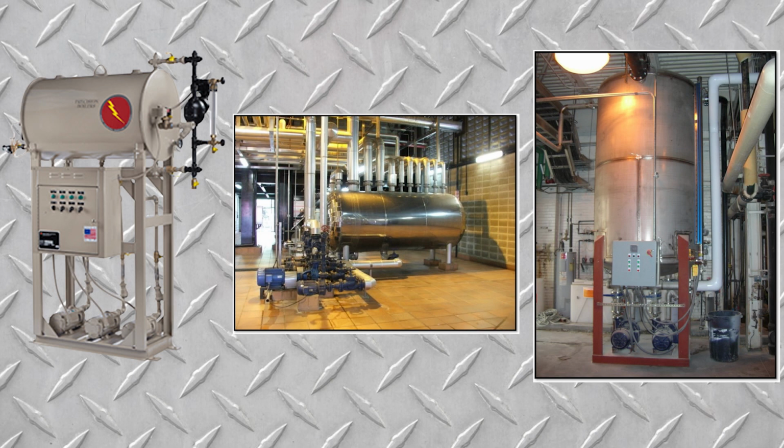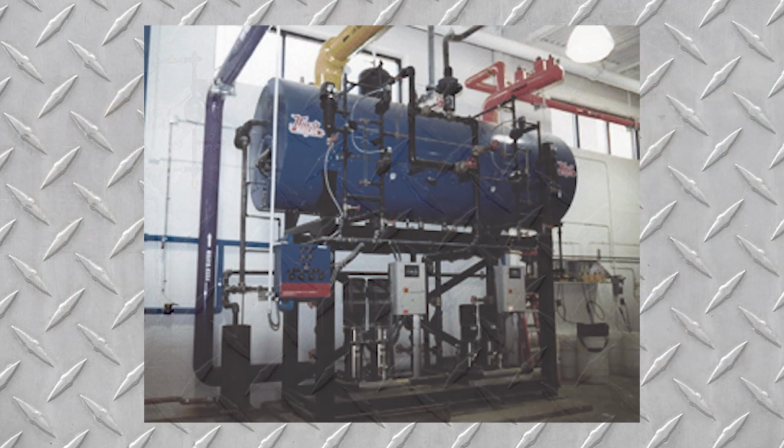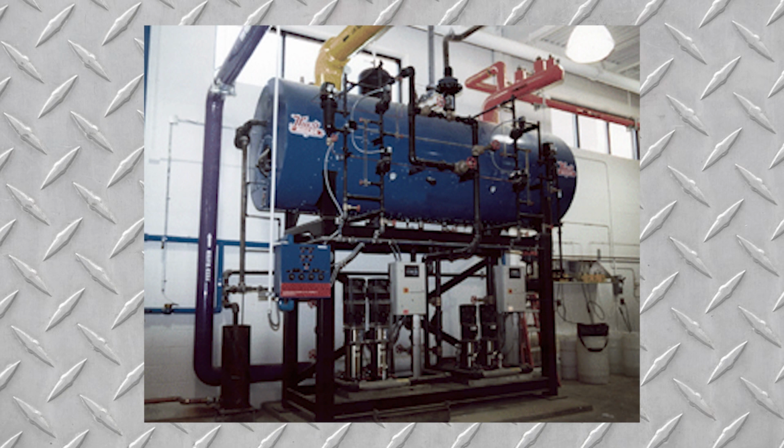It's necessary to remove gases that end up in the liquid water from all sorts of metallurgical activity or leaks or things of this nature. Often you're going to have CO2 and some other gases such as oxygen and nitrogen that would like to get out of the water before it goes back into the boiler. And this is done in the condensate return tank because the water is hot and at relatively low pressure, so you have the maximum amount of outgases wanting to leave the liquid. Deaerators are important and often not well understood, so I'd like to discuss them in a little more detail.